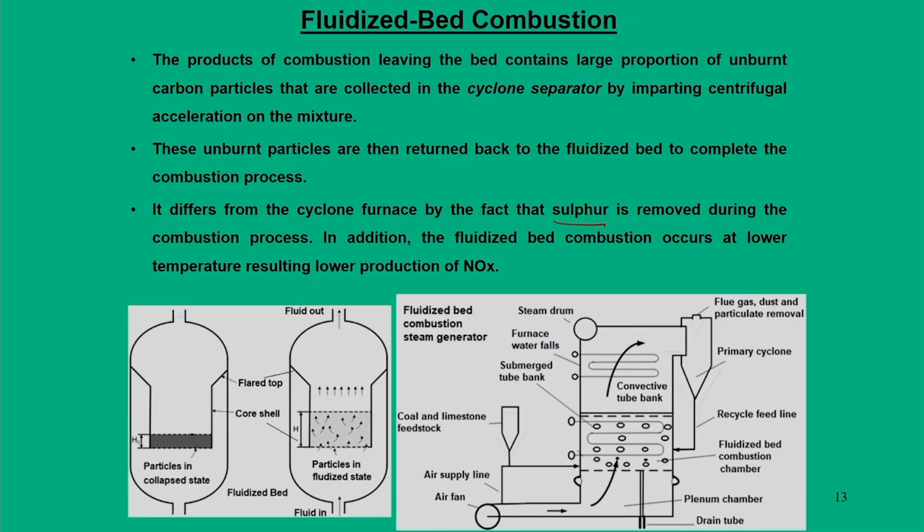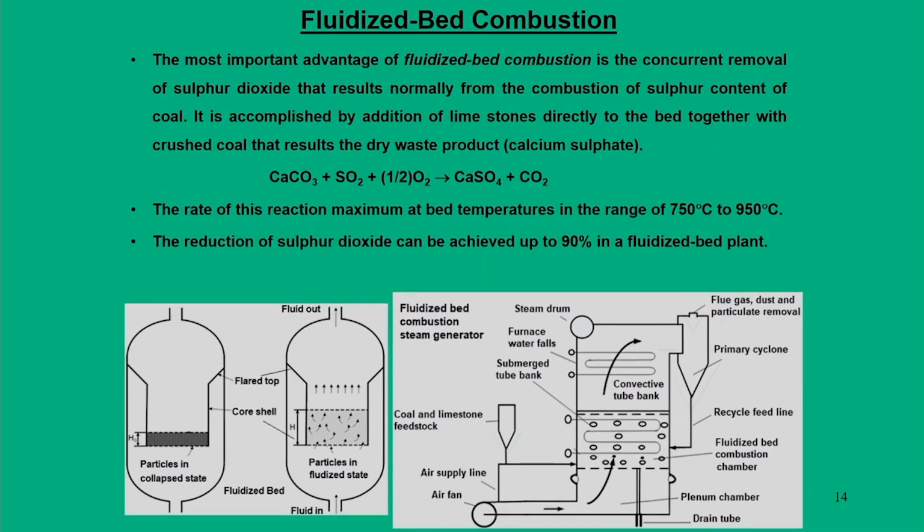Moreover, from an environmental viewpoint, this method gives lower production of NOx. Now, we will see how during fluidized bed combustion the sulfur content gets removed. When you use calcium carbonate CaCO3 with sulfur oxide and oxygen, and the combustion process happens, we get calcium sulfate and CO2.